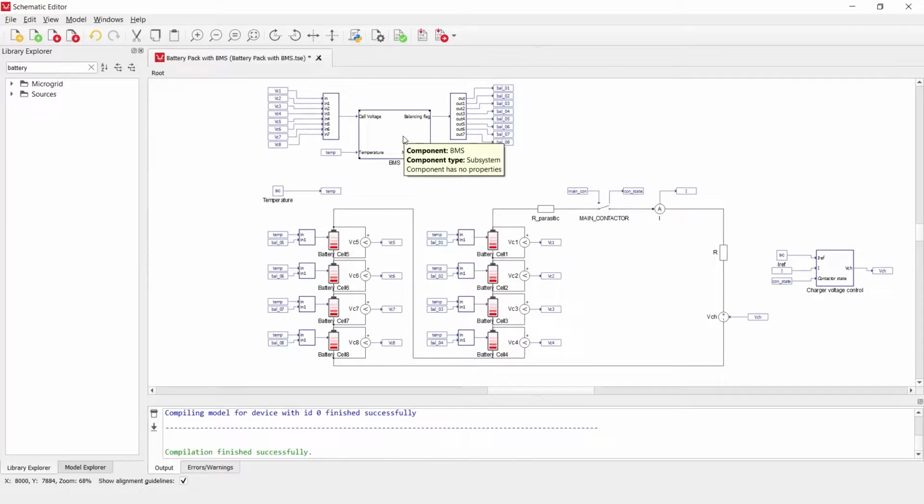This battery management system was created by me and it only represents the basic functionalities of the battery management system, meaning providing protection, providing measurements, and providing passive balancing of all the battery cells that have either too high a value or too high a difference compared to the rest of the battery cells. It also controls the main contactor for safety reasons, and it turns it off whenever a certain protection requires that the current stops flowing through the batteries.